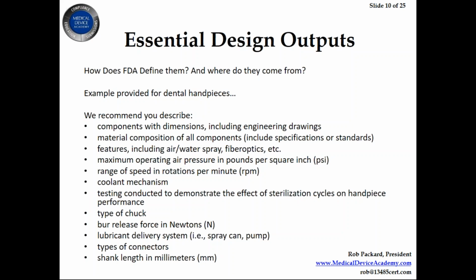And one example that I used earlier today in another webinar on device description, I was talking about dental handpieces. So the FDA specifically says in their performance testing section, we recommend that you describe the following parameters, and I bulleted those all out. So it's just a copy and paste from the guidance document, but these are all the things the FDA expects you to define in the product.